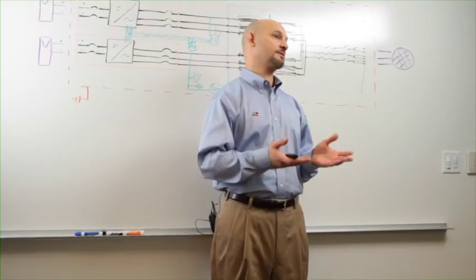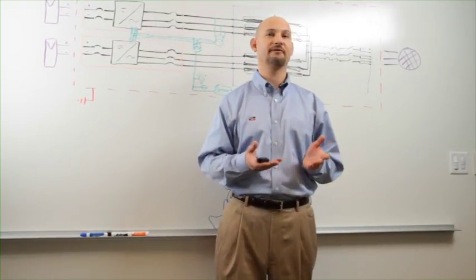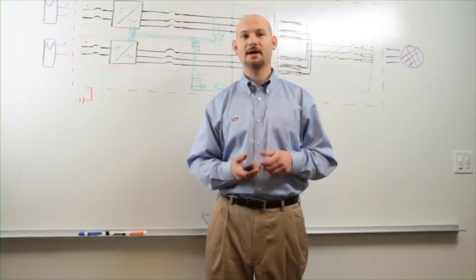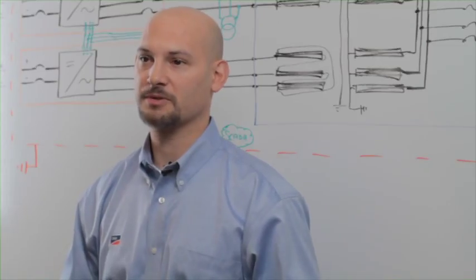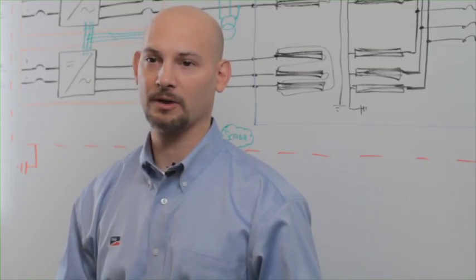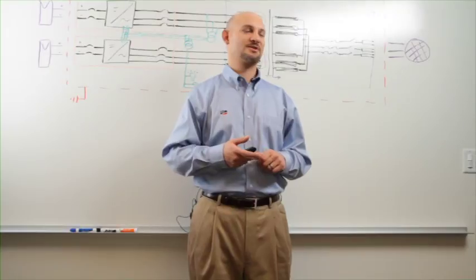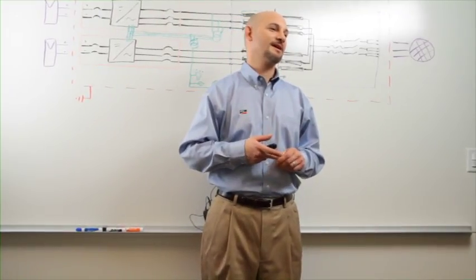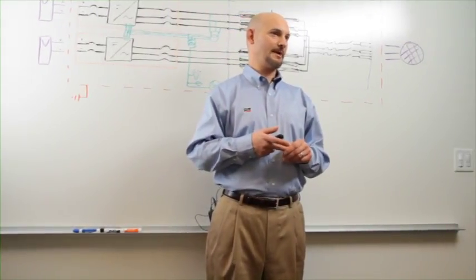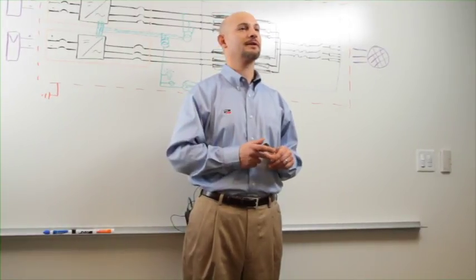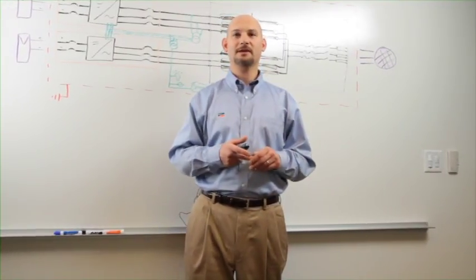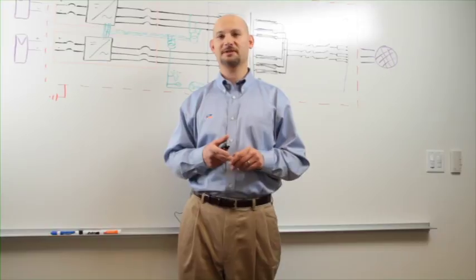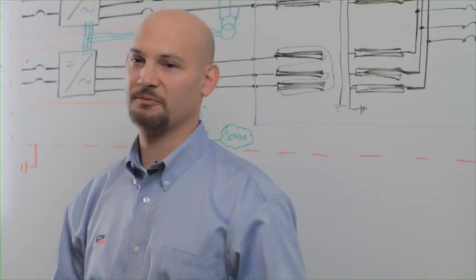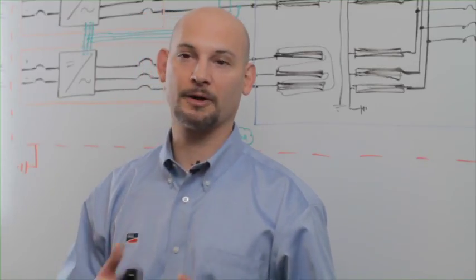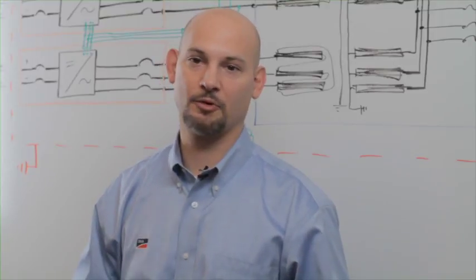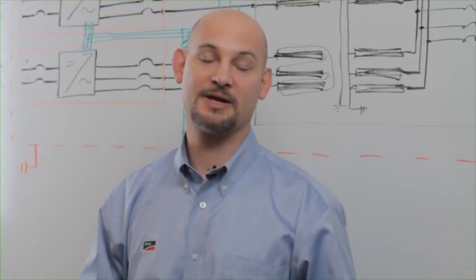And finally, the control power architecture on the station is configurable to include different power sizes of the transformer. You could include an additional transformer for feeding tracker motors, for instance, and of course communication media and power for SCADA systems. So in conclusion, the medium voltage solutions from SMA can provide you with a turnkey, high quality, high efficiency solution for large scale PV plants where it's very important to your ROI to deploy the solution and turn power on as fast as you can.